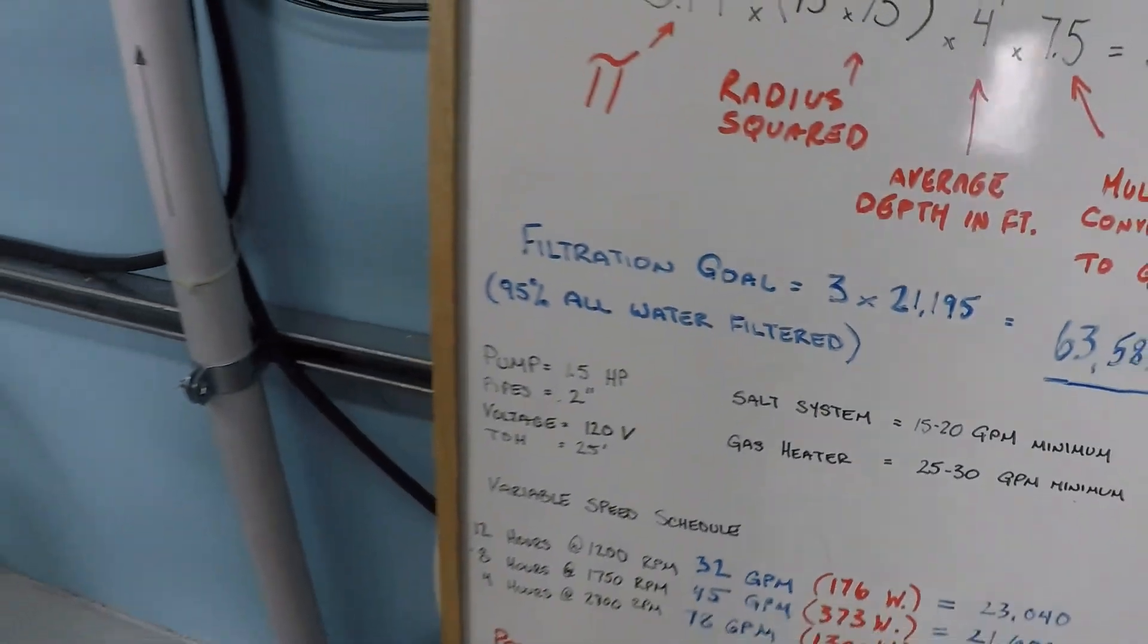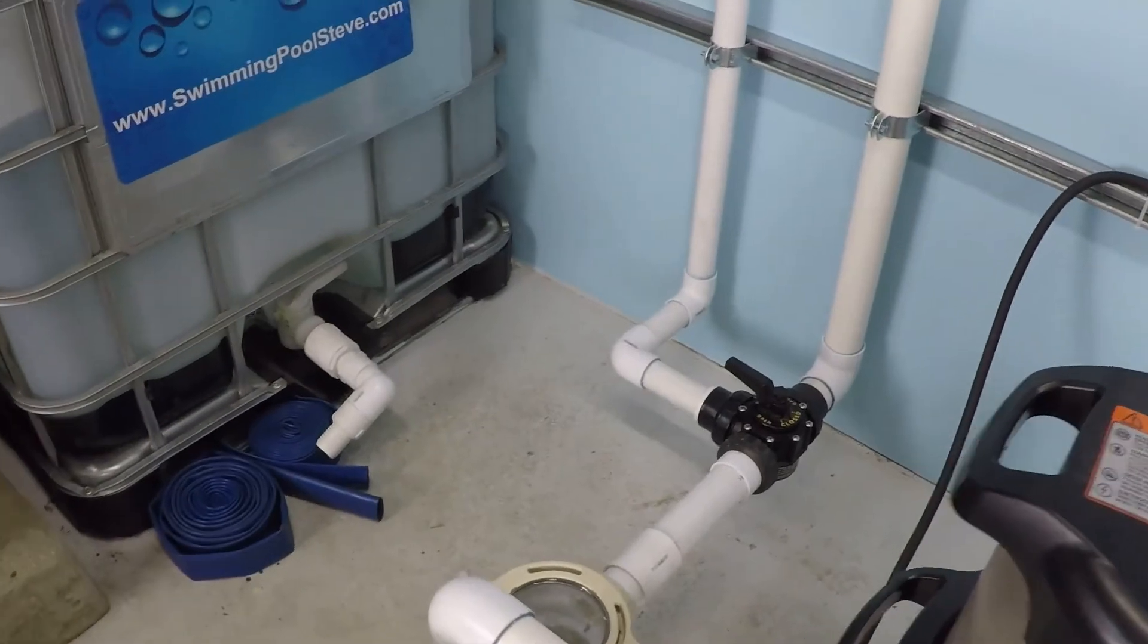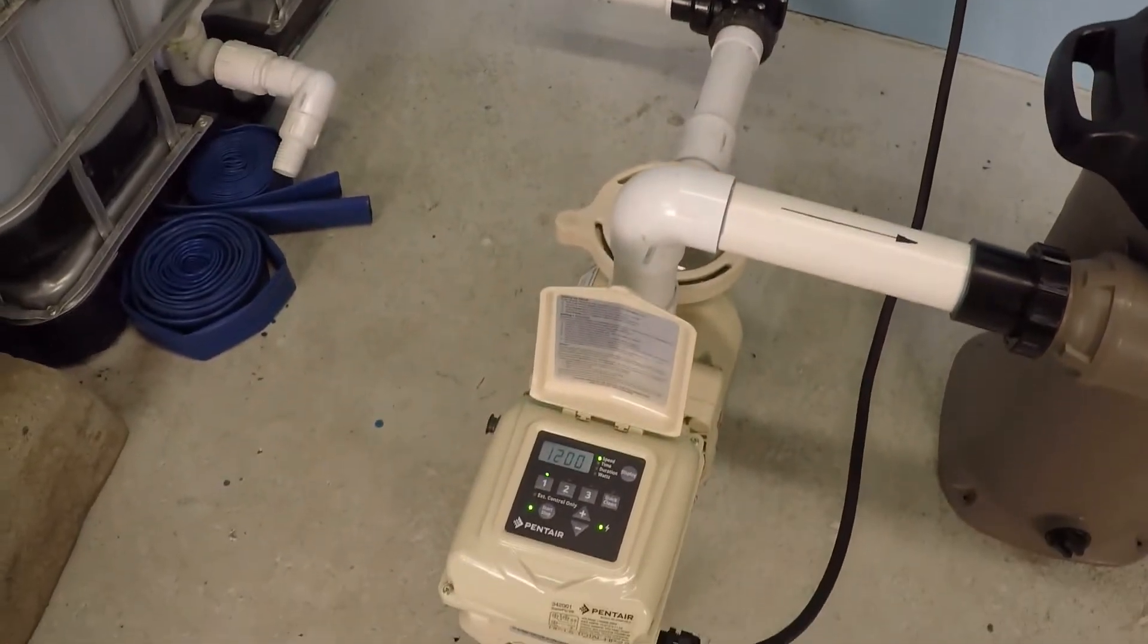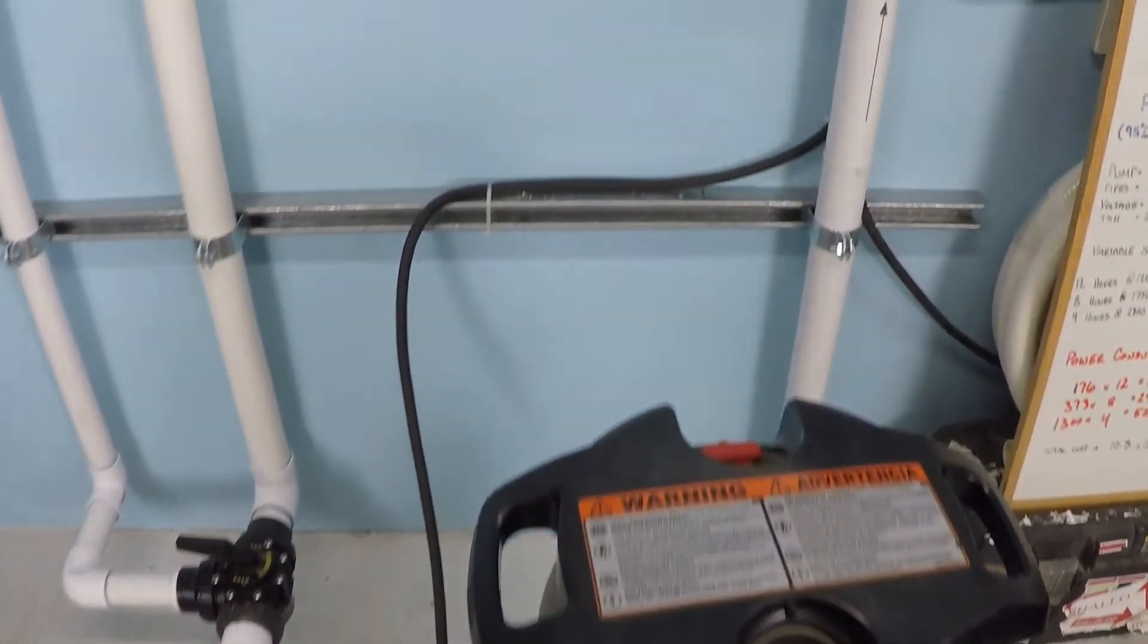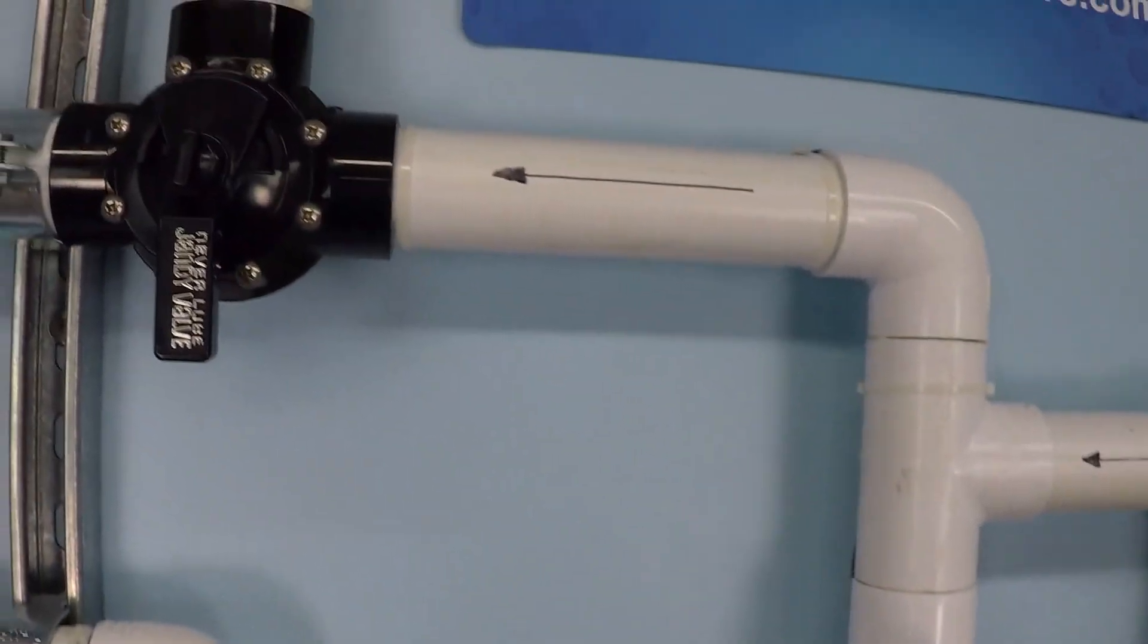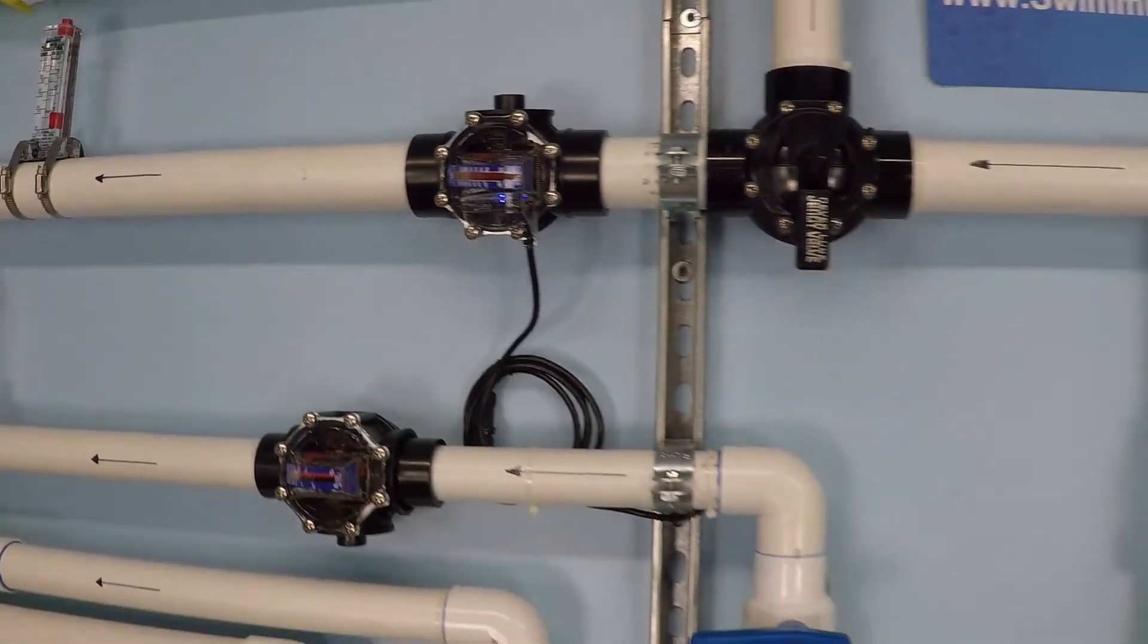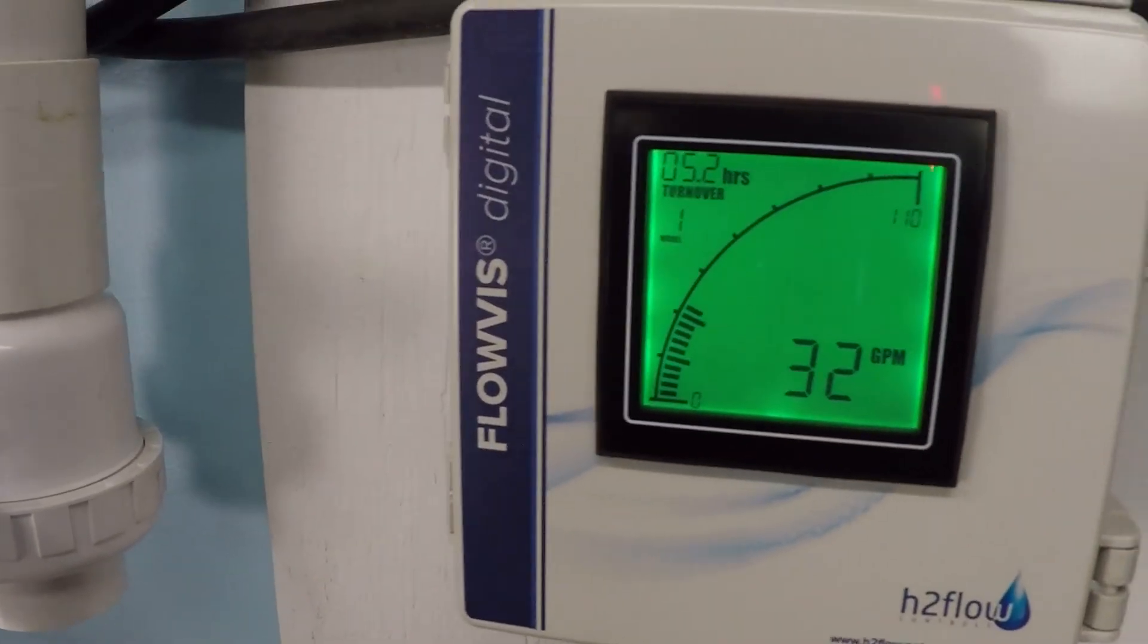Let's take a look at this system now. We have a two inch suction, two inch return on this system. There's the two inch suction line there. One and a half horsepower variable speed pump, 150 square foot cartridge filter. We're monitoring the flow rate today through this two inch line with this analog flow meter which has been adapted with this digital readout here. Very convenient.